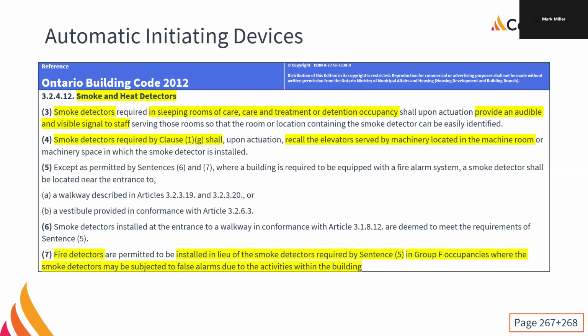There are exceptions to having to put smoke detectors in, because sometimes smoke detectors can be problematic. They can be quite sensitive. And if, because of the nature of the occupancy of the building, we're going to get a lot of false alarms, we can choose not to install the smoke detectors. We can put in alternate fire detectors. For example, Group F occupancies, industrial occupancies. If it's a welding and fab shop, there's going to be a lot of smoke in the air. Yes, we're going to have the smoke eaters and good ventilation and all that stuff, but there's still only so much you can do. So maybe we don't put the smoke detectors in. Maybe we put in heat detectors instead. So there's an exception that allows us to do that.